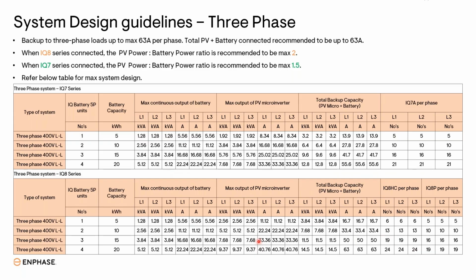If you do have more inverters, you can connect them, but you cannot exceed the 63 amps limit there. So if you have design issues or want to understand this more, you can connect with our regional technical team also. Say I'm installing a single battery, but I have more than 15 inverters, like 20 or 25 inverters. Can't I install a single battery there? Yes, definitely, with the IQ series you can install. We can do that also. That's no issue for us.